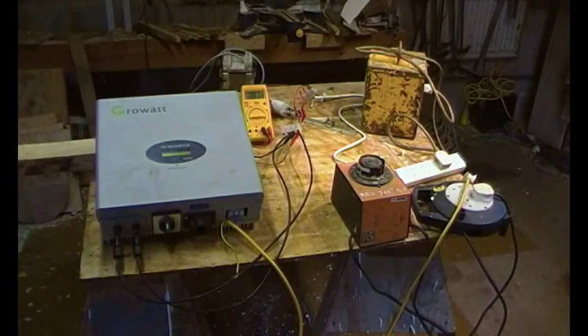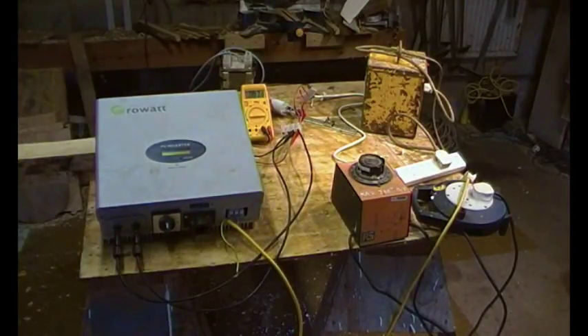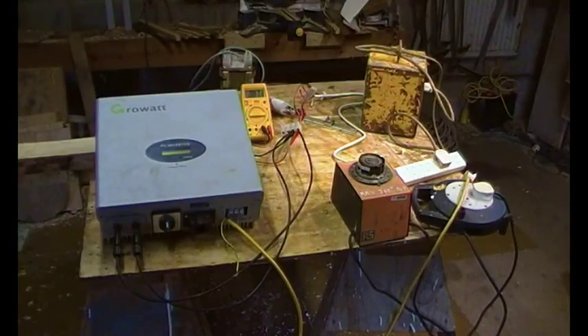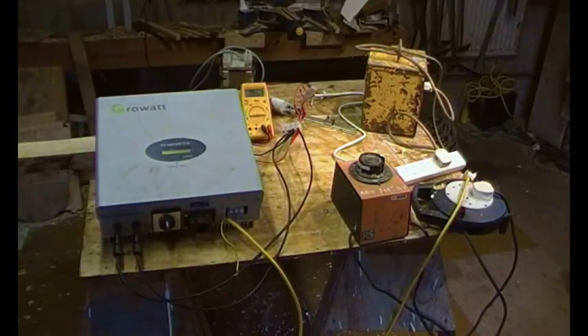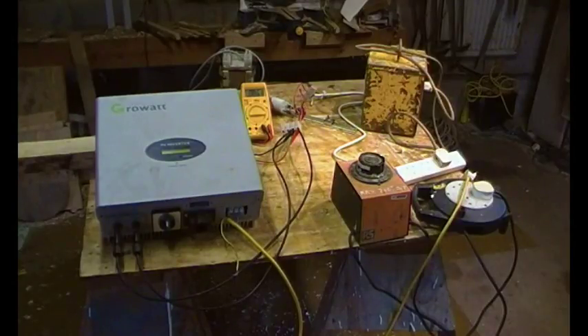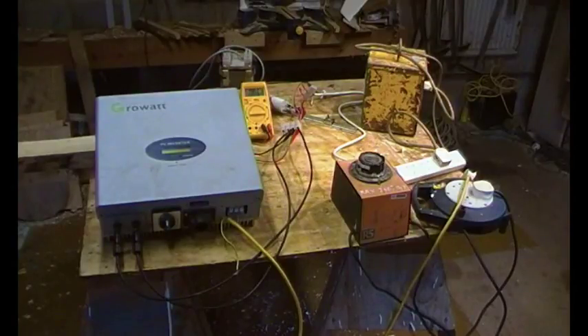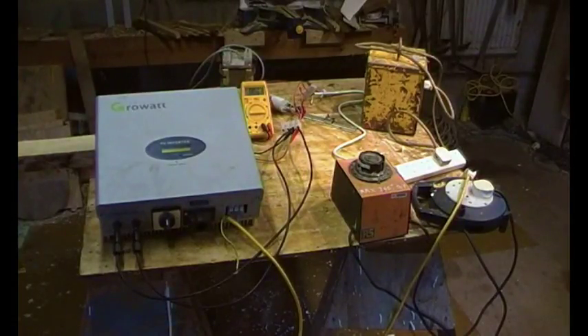So don't put it in the loft of your house, don't put it on the front of the house in full sun, because it will get very very hot and then it will switch off at full current through it being over temperature. And that means the relays are switching off full DC current, and that's how we can damage it. So over volts, over current, over temperature - all three of them definite no-nos.